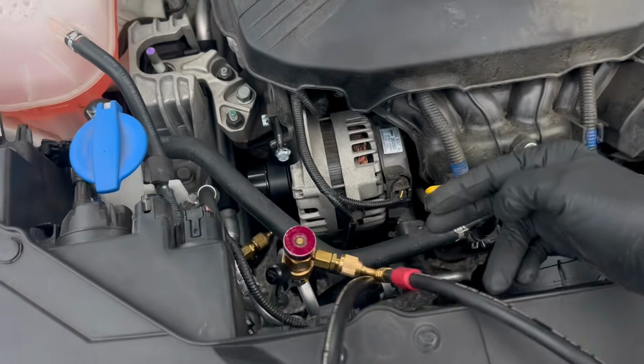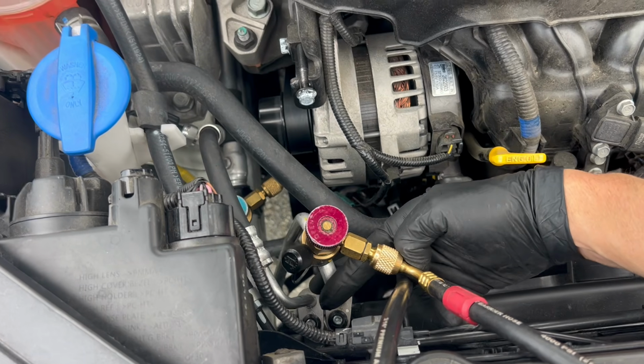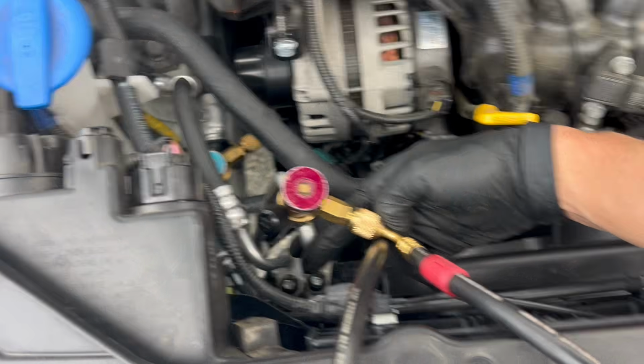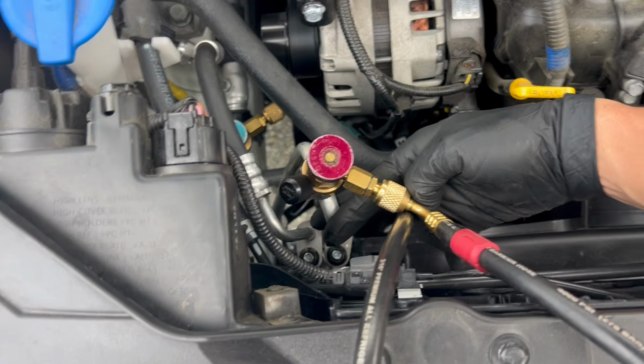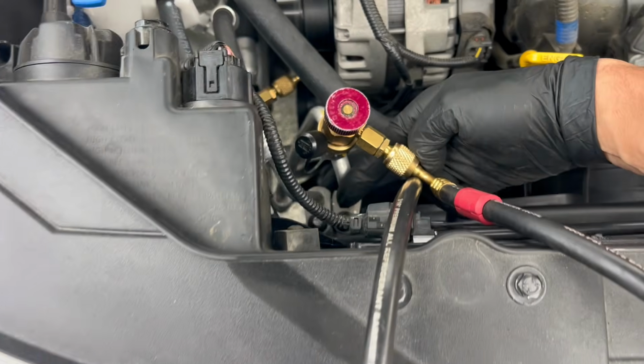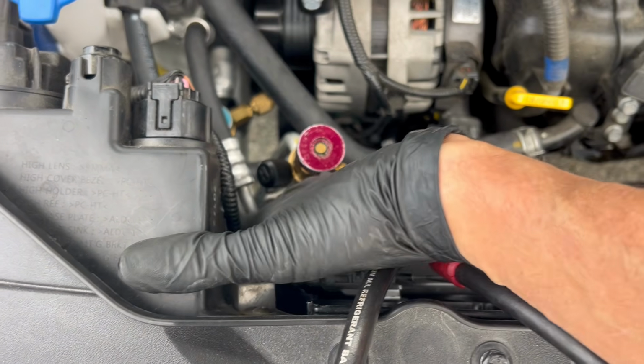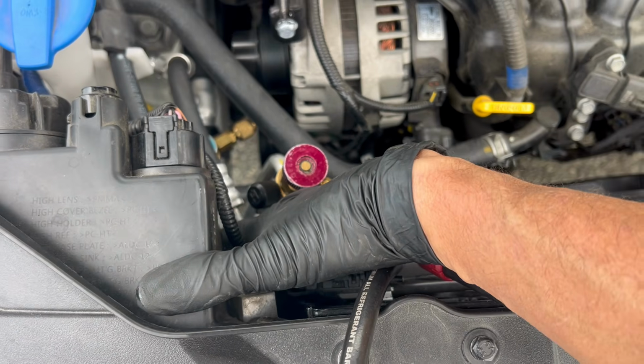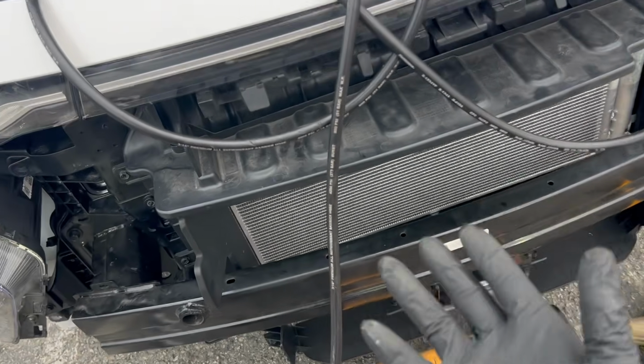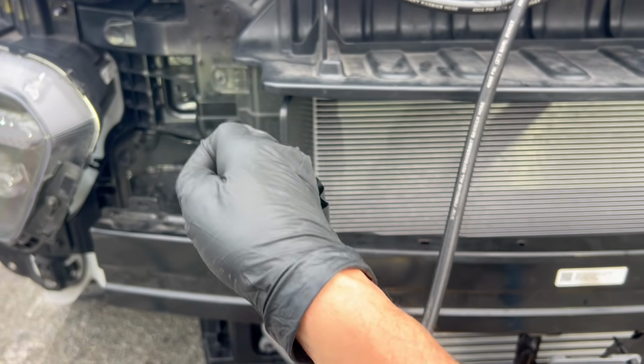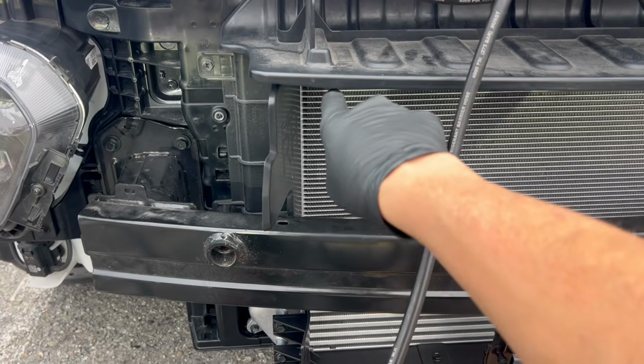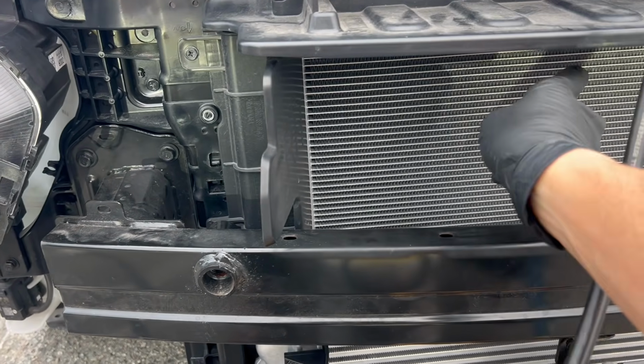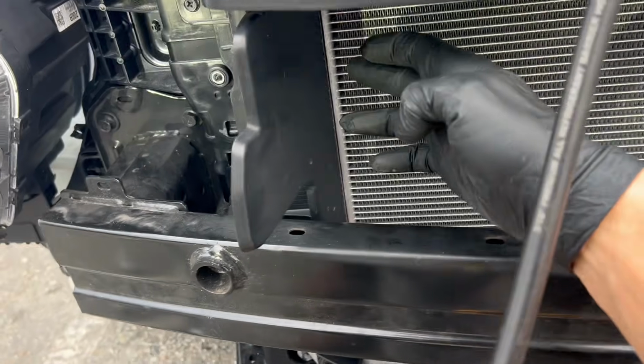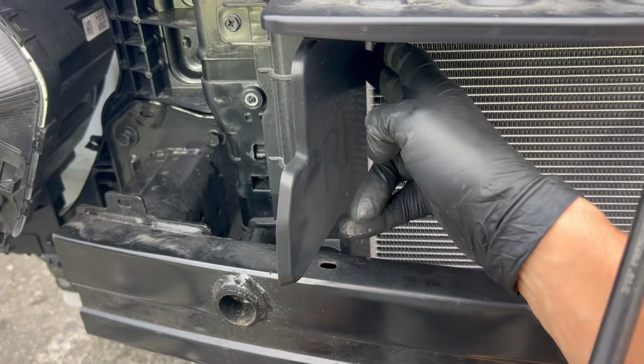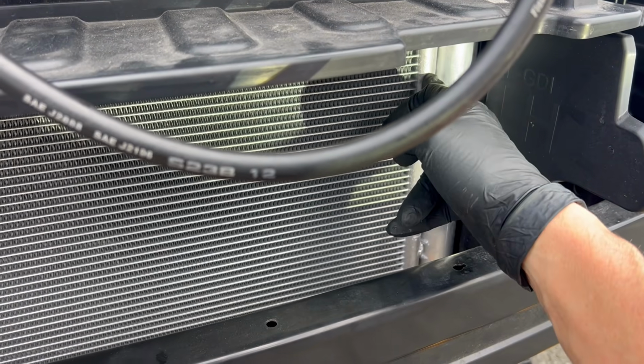Temperature sensor, same thing. If I had 400 psi right here and I put my pressure transducer in there, let's say the temperature would be 210 degrees. I'm just pulling a number out of thin air. Okay, we have 210 degrees coming out, but then you see the liquid line coming out. I put another temperature sensor and I clamp it onto that line, and it's 55 degrees. Well, you know something is acting like an expansion valve, a restriction, and that's the metal particles or plastic or Teflon particles coming out of whatever compressor is on there, packing up, building up pressure, but blocking these little tubes so they can't pass. Now, you could put a temperature sensor and you could touch right here and you'll see it's 200 degrees. You put the temperature sensor and you touch right here and you see it's 70 degrees.